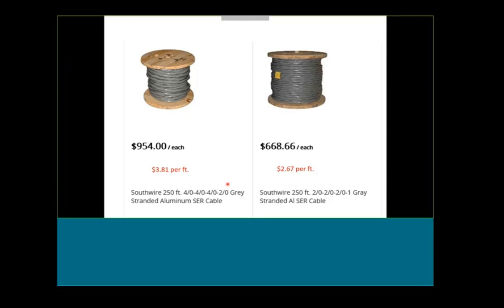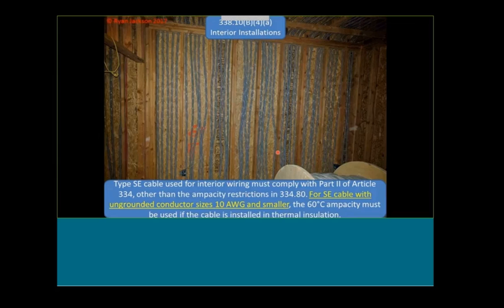Between those two rules, you might be able to go from 4-aught under the 2014 to 2-aught in the 2017. That's a substantial difference. Now, I don't know what people are really paying for cable, but I just went to Home Depot online and grabbed a screenshot. 250 feet of 4-aught costs $950. 250 feet of 2-aught costs $670. So you're saving about a buck and a quarter a foot, give or take, times five stories, a couple hundred units. You're talking about a substantial cost saving.